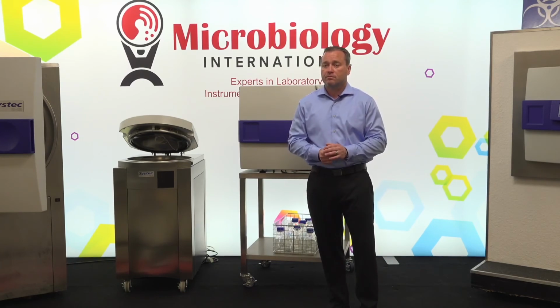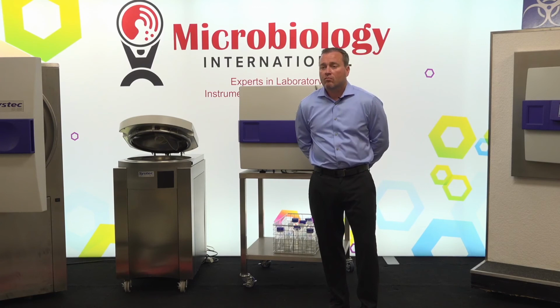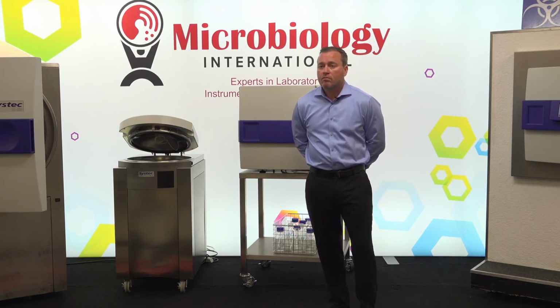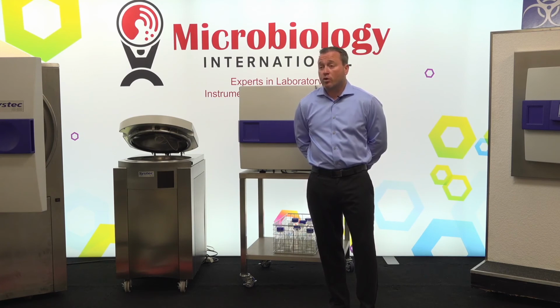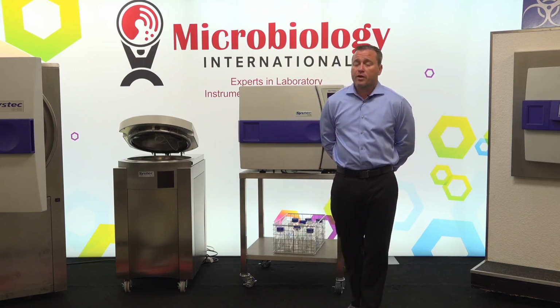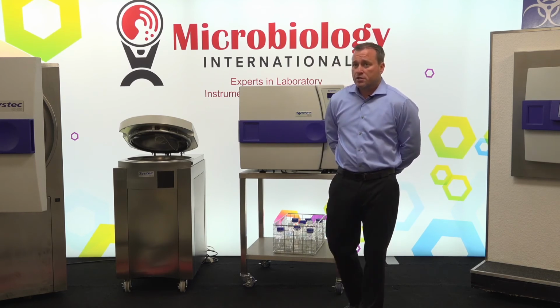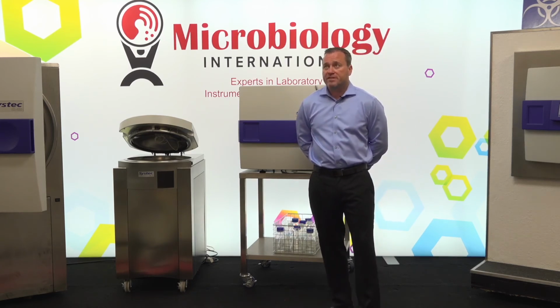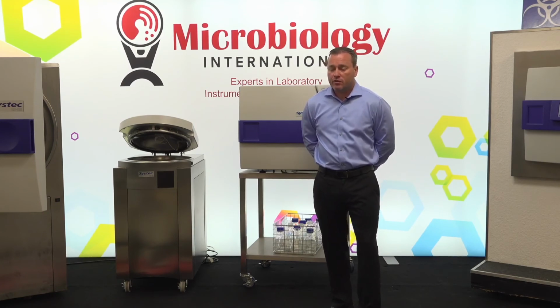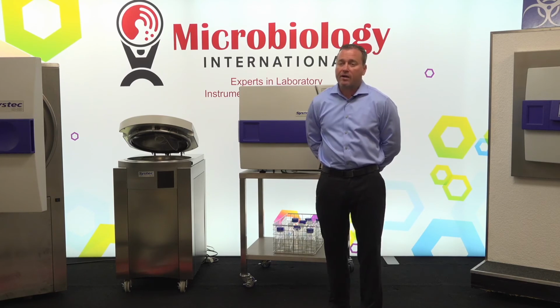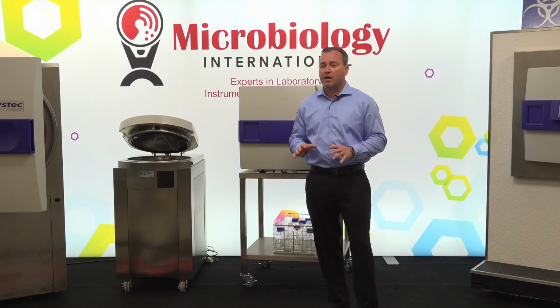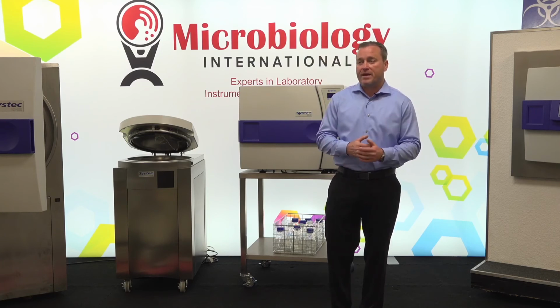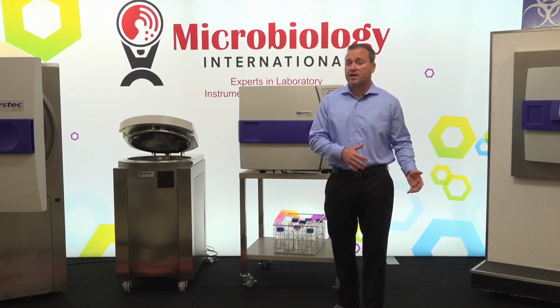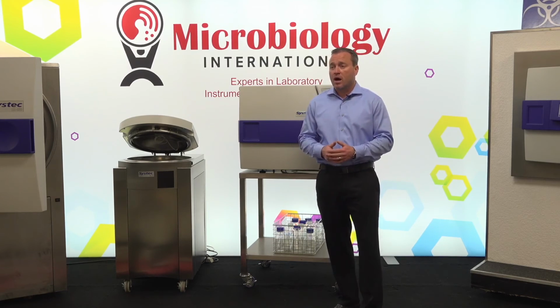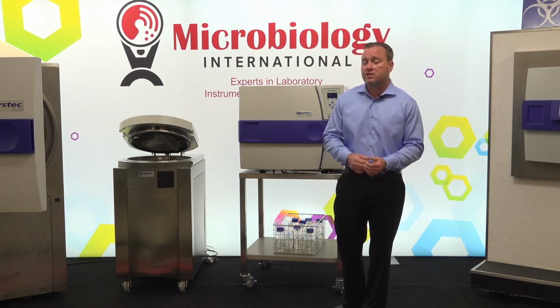All right, and then assuming yearly maintenance schedule, what would you say that the average lifespan of a unit is? I still have units that we sold originally, so every autoclave vessel that we're going to look at should be qualified for 15 years. That is the operational standard for the industry, 15 years on a vessel. However, we know that they're going to operate a lot longer than that. There are no parts on any of our autoclaves that have planned obsolescence. So basically, we have units that we sold the first year that we sold Systec instruments that are still in operation that we actively service. So that 15-year mark, easily we could achieve 20, 25 years with one of these systems.